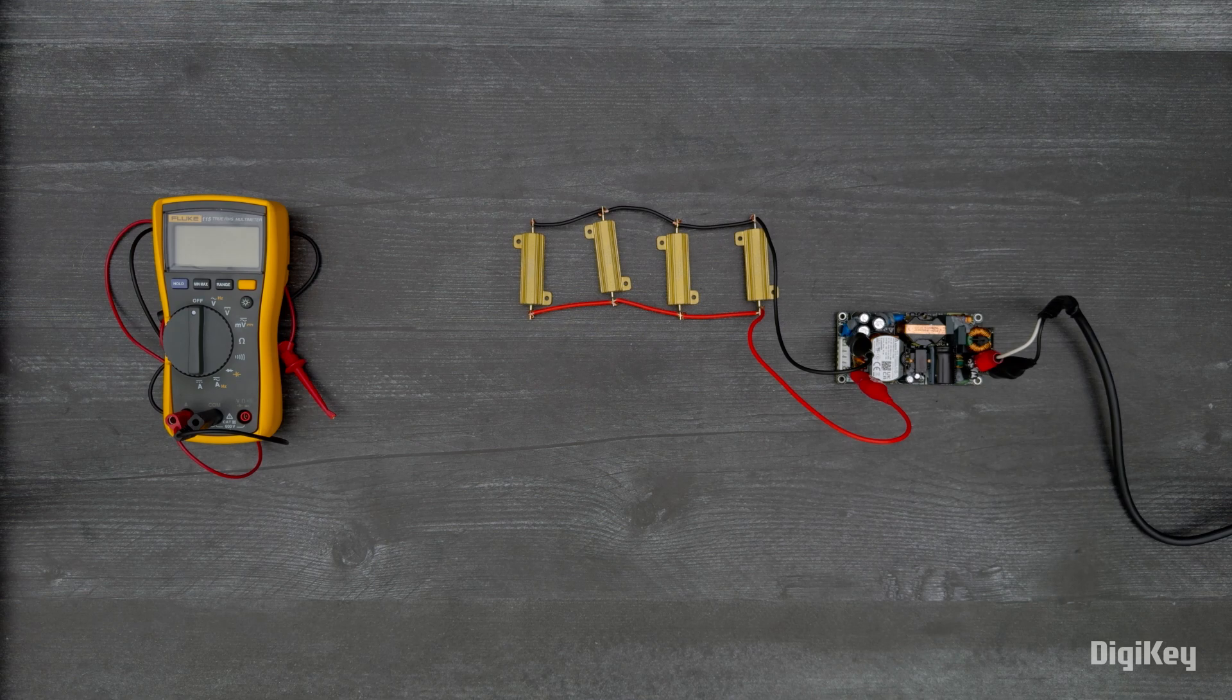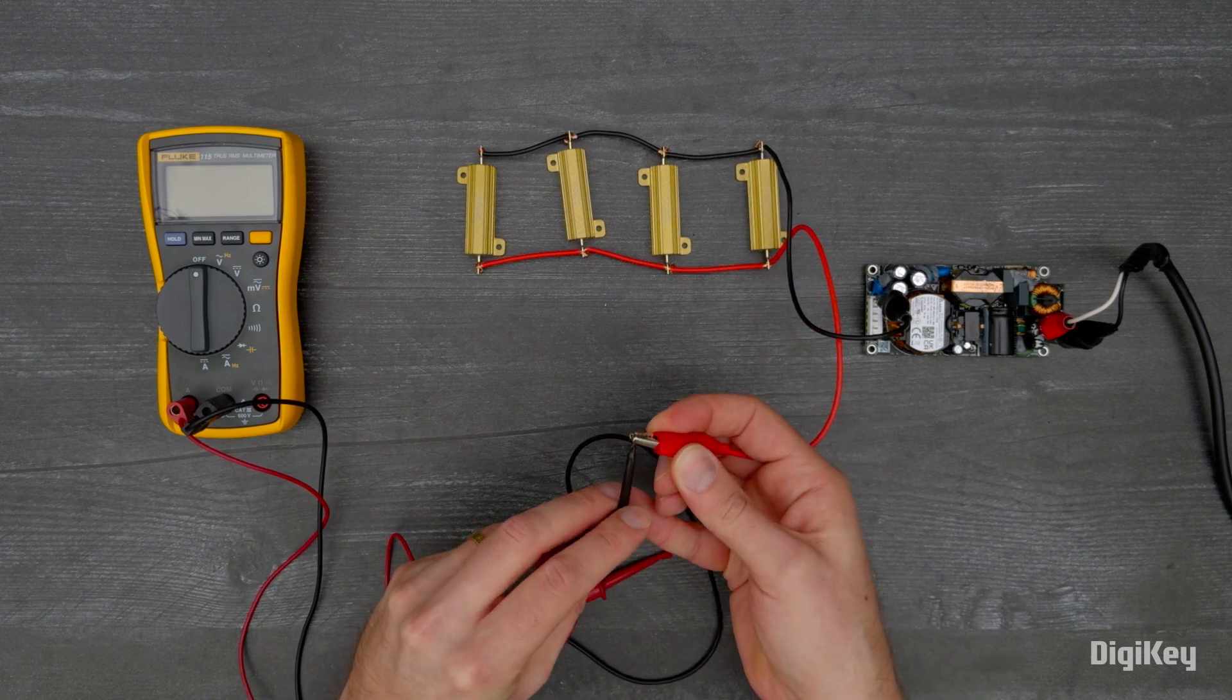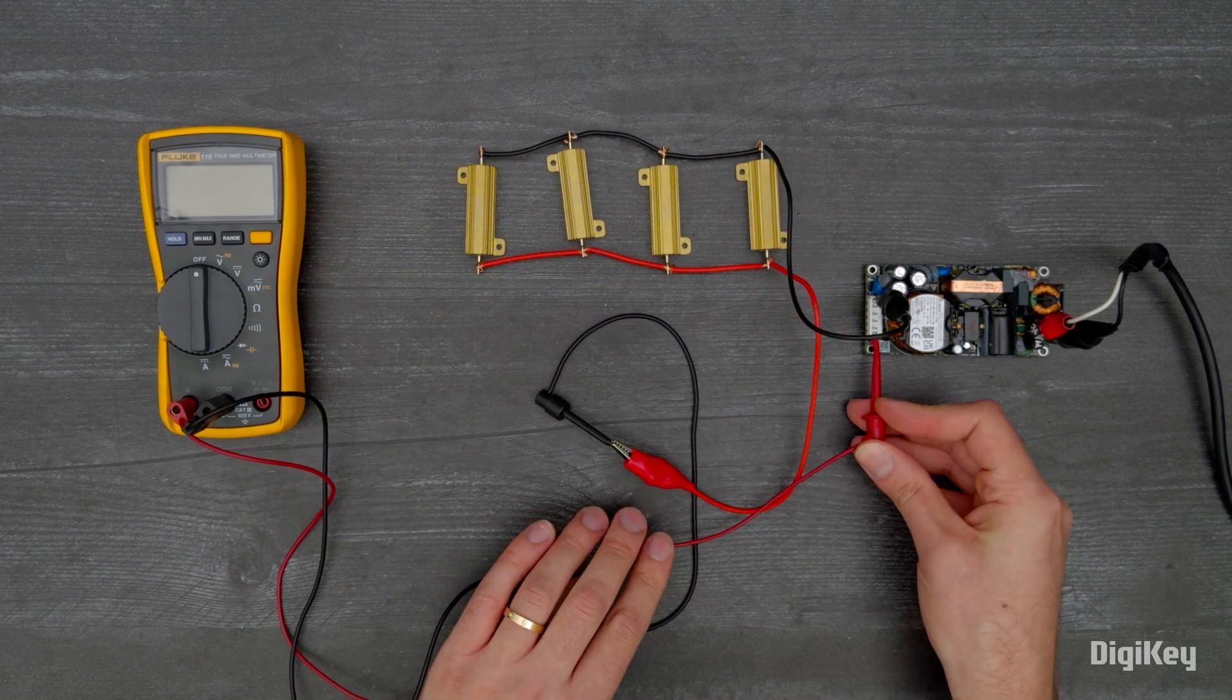To measure the output current, disconnect the input, then disconnect the pin four connection on the output connector. Now connect a DC ammeter in series.